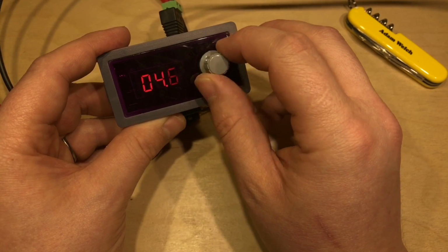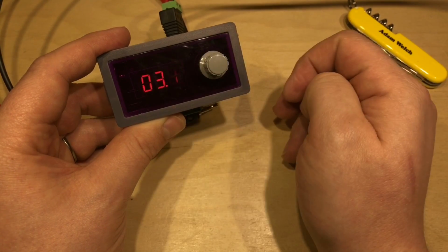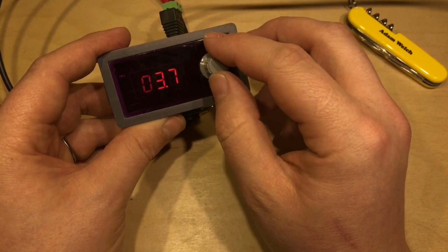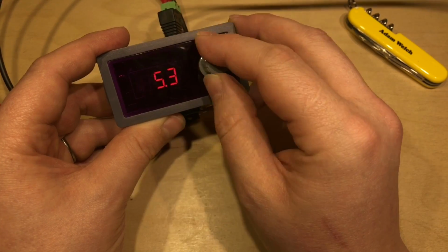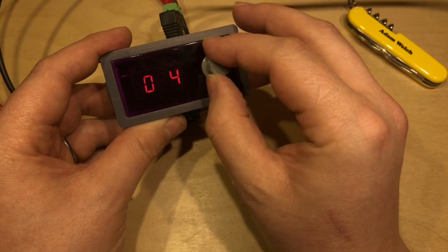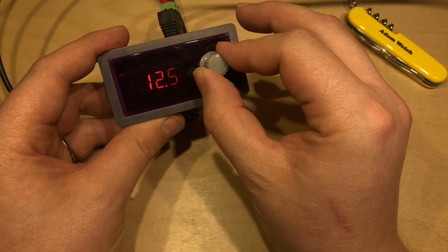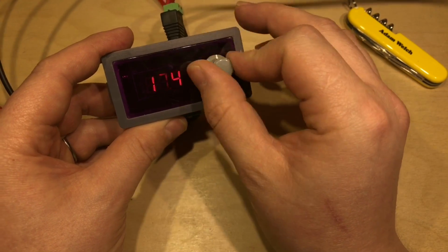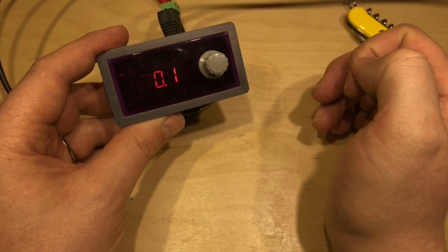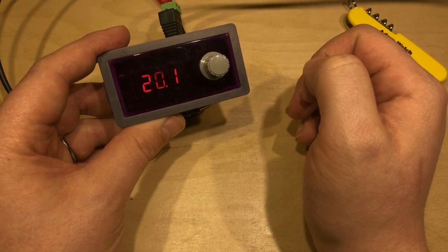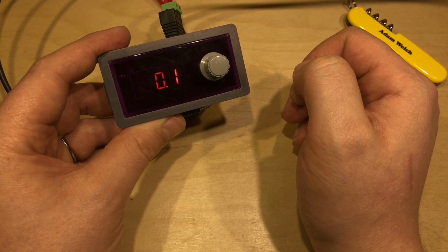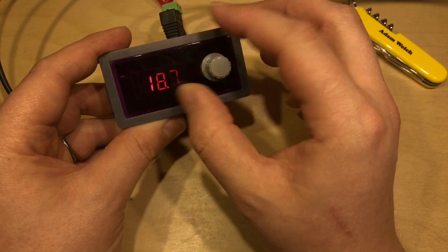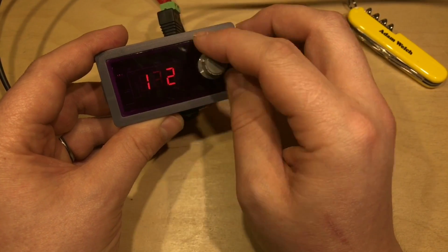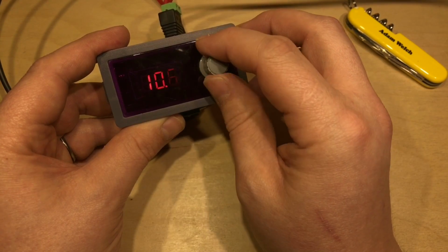So let's turn this 5 turn potentiometer. So we've got all the way down there to 3.7 milliamps. And if we keep turning it, we get all the way up to 20.1 milliamps. So without further ado, let's set it to, I don't know, 10 milliamps. And plug in a meter.